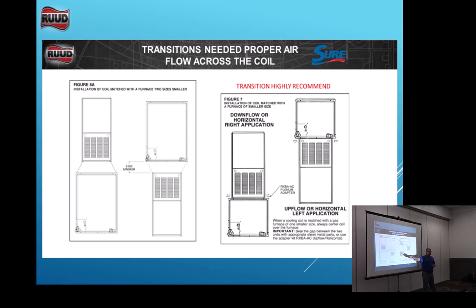What about a horizontal application? In order to make that work in a horizontal application, if we're not going to use a transition, we got to have a different size heater stand on the furnace and a different size heater stand on the coil. Are y'all going to take 2 different size heater stands? Come on, guys. I know. You grab one and you just slide it up there, and then we got 4 inches hanging on the top, right? And block it off. Now we got 4 inches of air that's not going across that evaporator coil, along with the turbulent air that's going inside the evaporator coil, right?